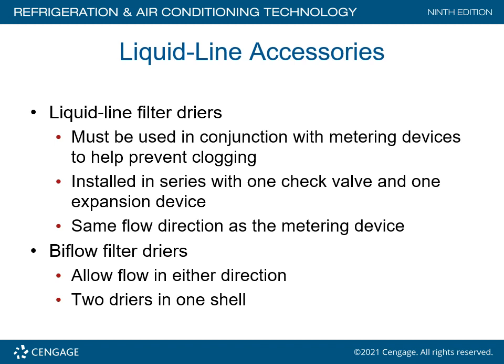Now the question has been asked in the past, can I use a bi-flow dryer on just a split system air conditioner if I don't have a single flow design on an air conditioning system? Sure, it's more expensive. That being said, the bi-flow dryer is absolutely critical for the proper operation of the heat pump, whereas on an air conditioning split system or package unit, the flow of the refrigerant in one direction is what we need to maintain.